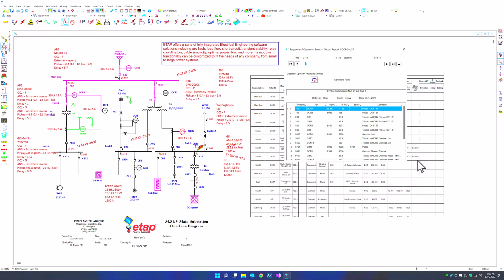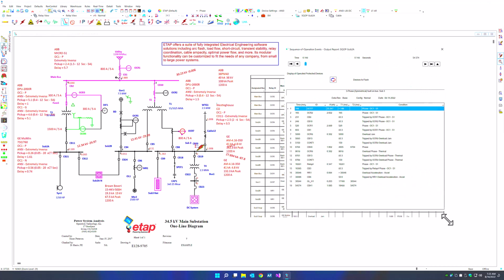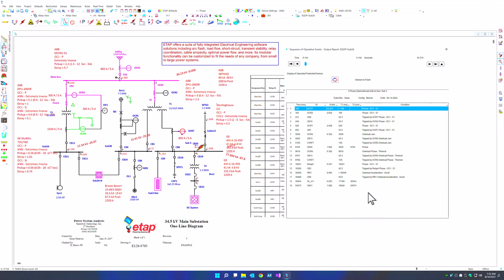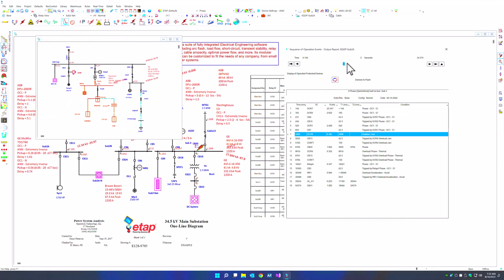Once you run the Star sequence of operation, you essentially get the sequence of operation event list. From this list, you can pick a particular component, and the program will essentially move the slider, letting you know at what time that particular event happened, and in this case it happens to be at 5 seconds, and will also highlight and show you which device actually operated during that time frame.